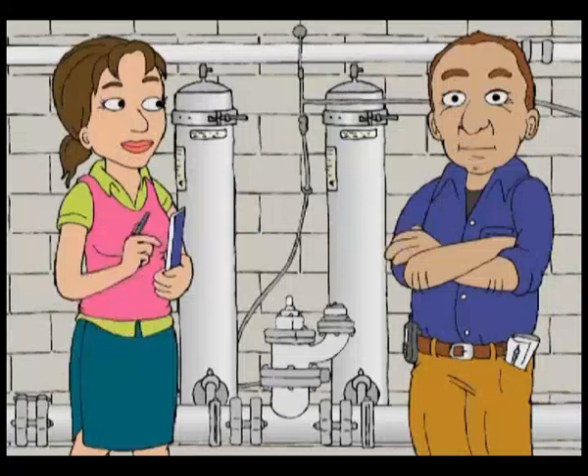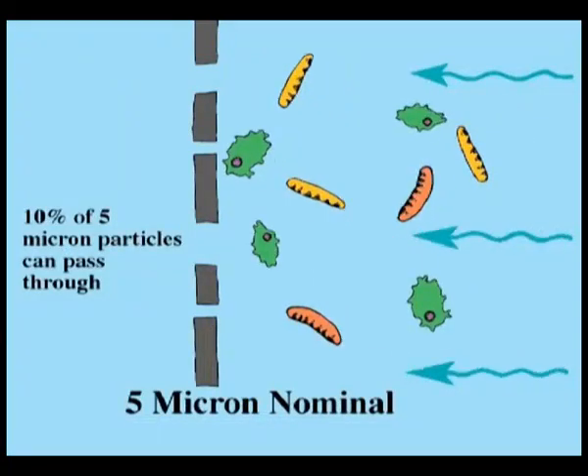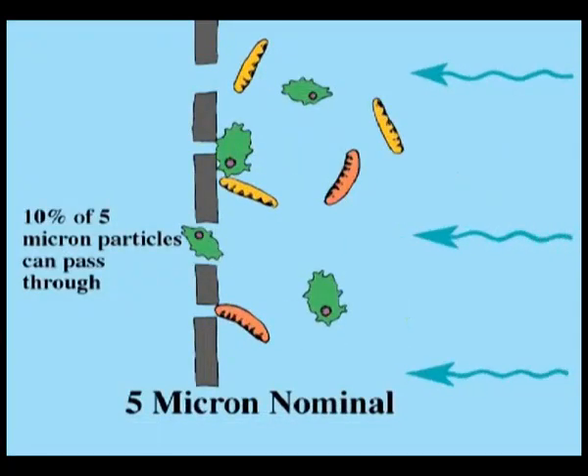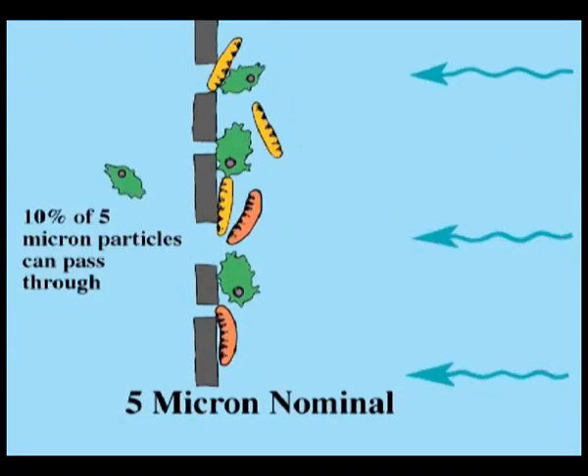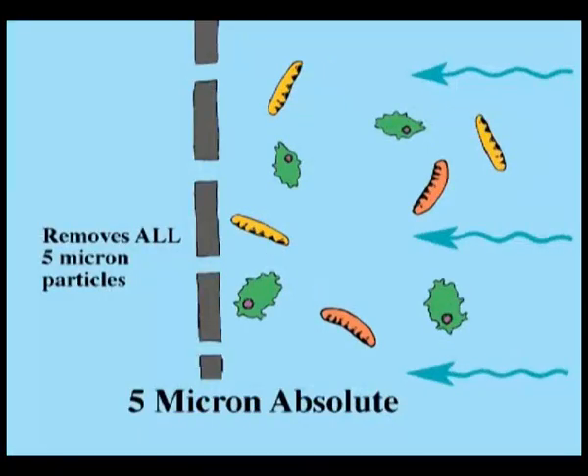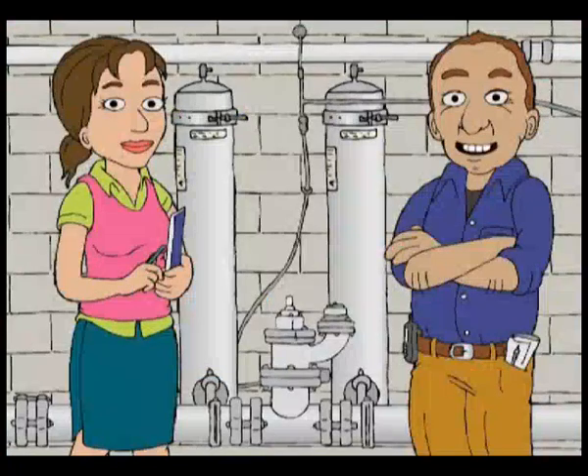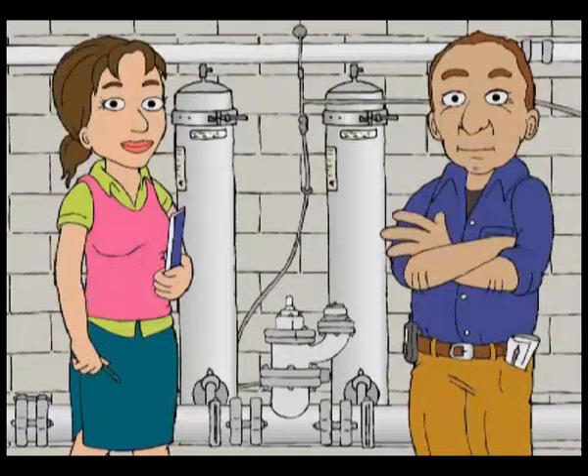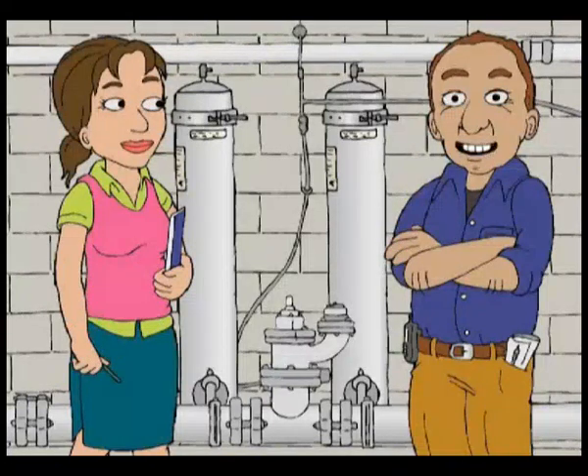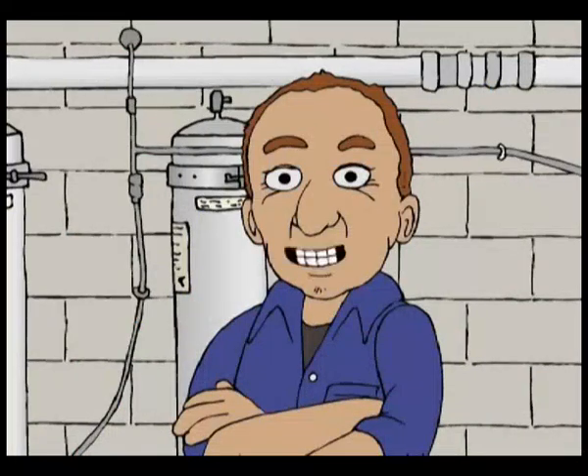Cartridges are categorised as either nominal or absolute. If a cartridge is 5 micron nominal, then it will remove 90% of the 5 micron sized particles — some will pass through. If it's 5 microns absolute, then it will remove all 5 micron sized particles. Some water supplies use a 20 micron cartridge filter to remove larger material, followed by a 1 micron cartridge filter which removes protozoa cysts. Usually the 20 micron will be nominal but the 1 micron cartridge will be absolute.